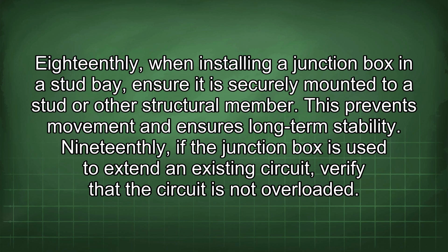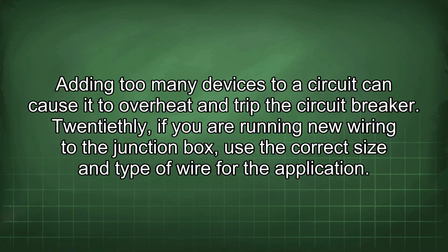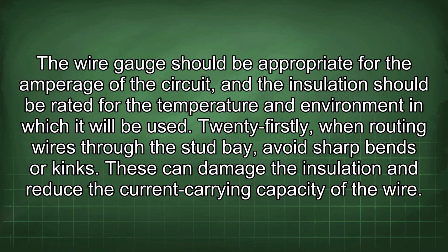19thly, if the junction box is used to extend an existing circuit, verify that the circuit is not overloaded. Adding too many devices to a circuit can cause it to overheat and trip the circuit breaker. 20thly, if you are running new wiring to the junction box, use the correct size and type of wire for the application. The wire gauge should be appropriate for the amperage of the circuit, and the insulation should be rated for the temperature and environment in which it will be used.